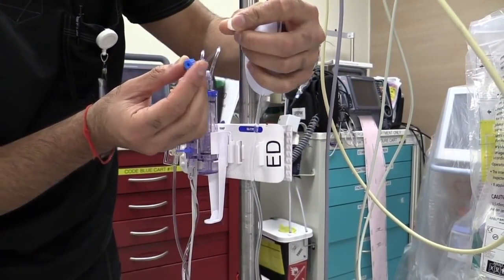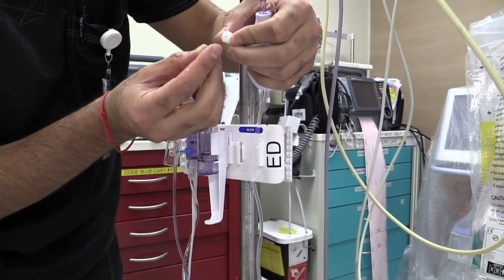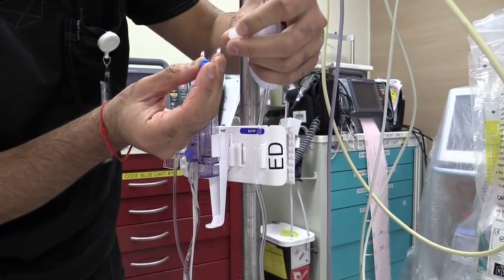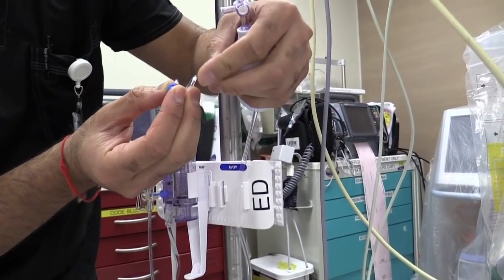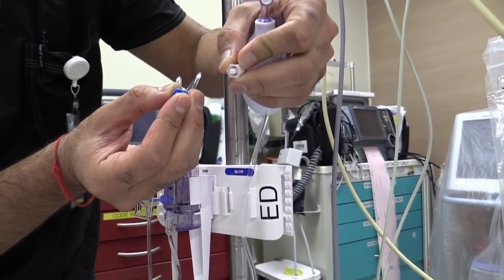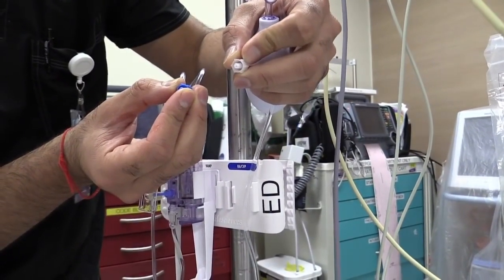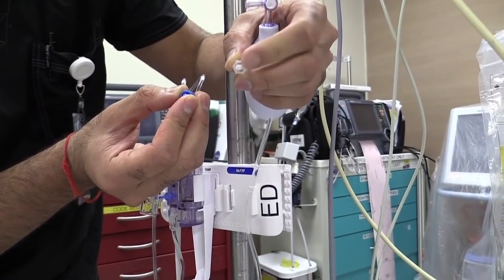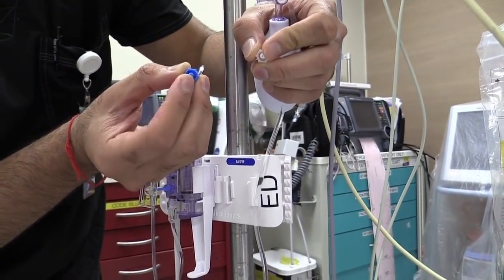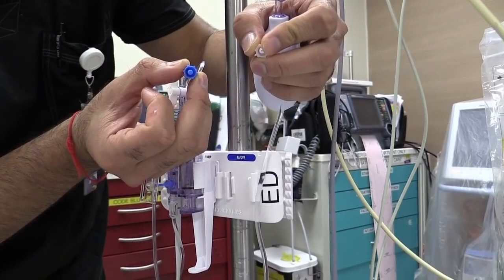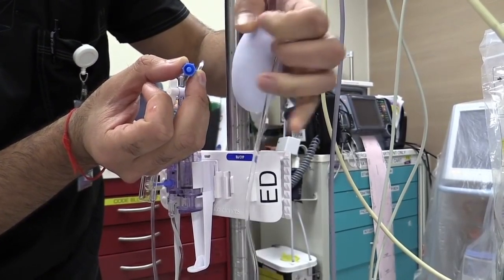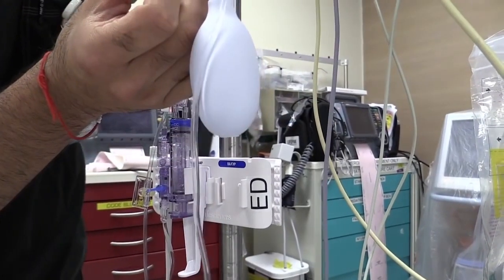This cap right here looks the same from this side, but it actually does not have a hole on that side, unlike this cap, which actually has a tiny little hole in it, which allowed that fluid to escape before. So we're going to take this one off and put this one back on so there's no more fluid or air that can actually get in or out of the system.